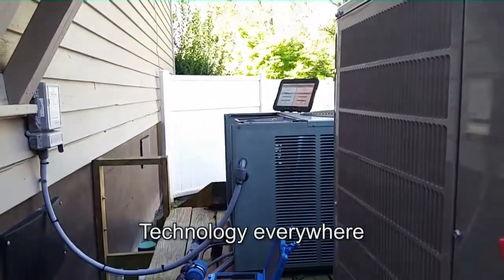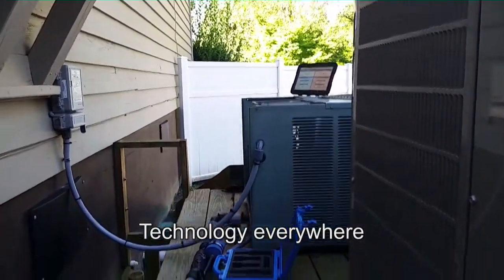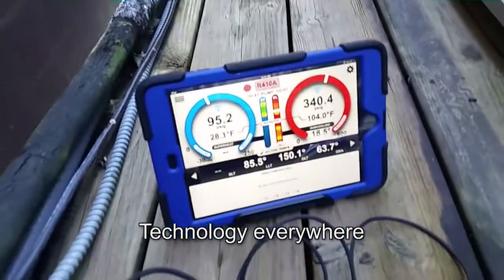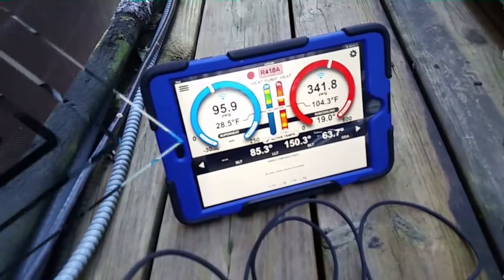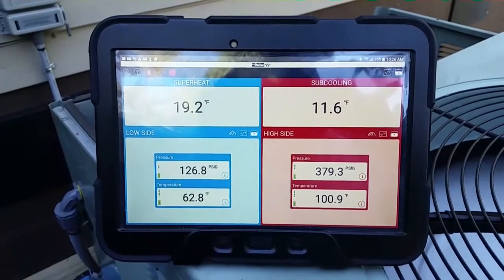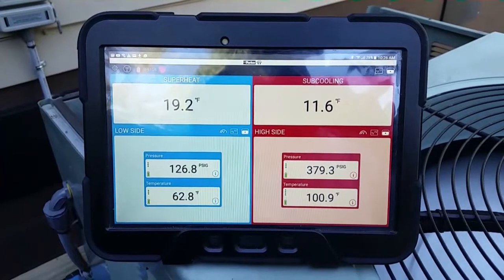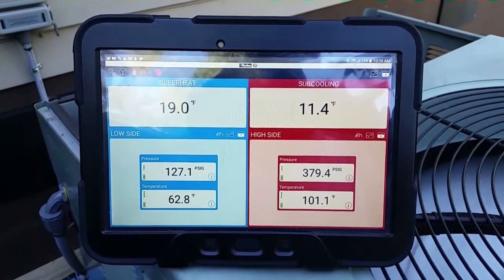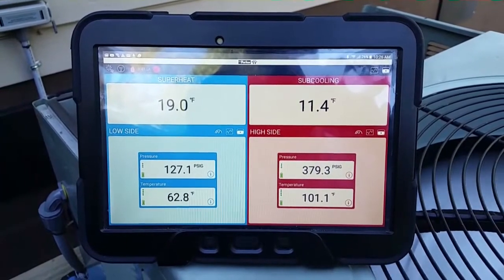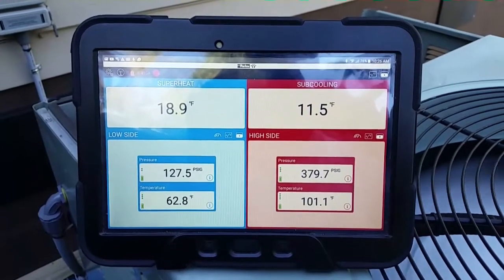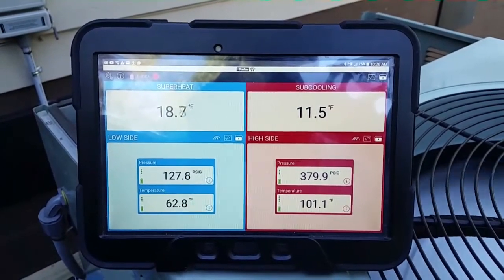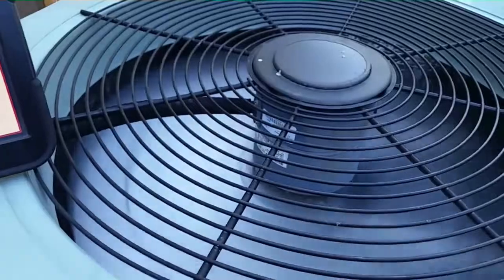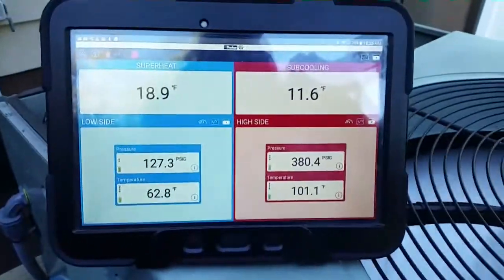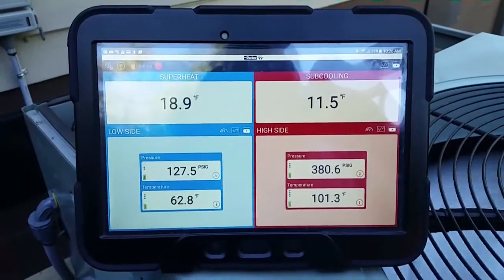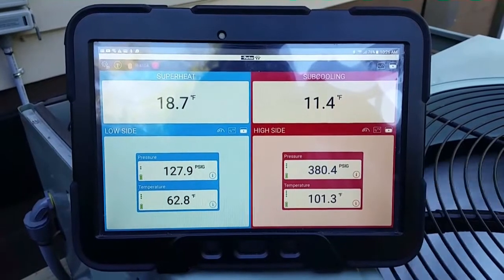Over on the other, we have our smart tool on the Rheem. We'll go check it in just a second. We'll let this one build back pressure until it gets to its stable point. The Rheem here, you can see, has 11 degrees subcooling, 19 degrees superheat. Looks real good. 379/127. Everything's looking really good for the Rheem. It's been running here for about 10 or 15 minutes. ECM fan motor on top. Standard single stage compressor matched up with a variable speed air handler.